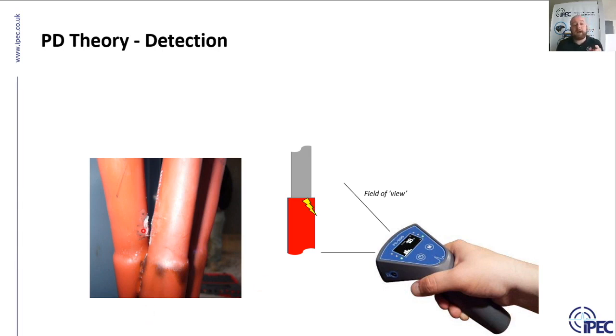This picture on the left is actually quite a nice picture. It shows another type of partial discharge that can occur. This is not caused by, well, I suppose to a certain extent it is caused by weak insulation. But the main problem here is that the 3 phases are coming inside the termination. The insulation has been stripped back a little bit too early, if you like, and the phases are too close together. So we've got these 2 phases, this is where some of the insulation is ending. The insulation here is very thin, and the phases are too close together, and so you get this discharge occurring between them. Now, of course, visually we can see this, but before it was visual, the ultrasonic sensor would be able to pick it up.